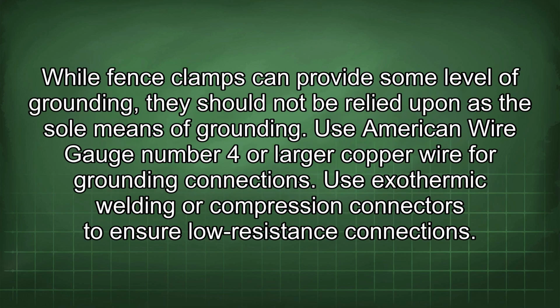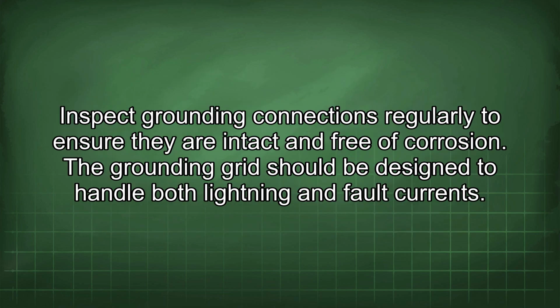While fence clamps can provide some level of grounding, they should not be relied upon as the sole means of grounding. Use American wire gauge number 4 or larger copper wire for grounding connections. Use exothermic welding or compression connectors to ensure low resistance connections. Inspect grounding connections regularly to ensure they are intact and free of corrosion. The grounding grid should be designed to handle both lightning and fault currents.